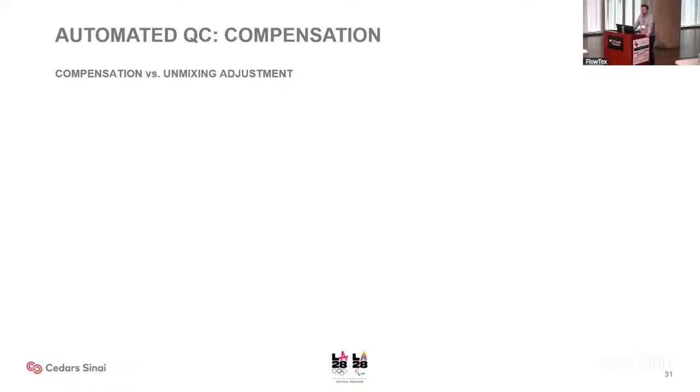In our lab, we see day-to-day drift, especially in the far red channel. So it's something that needs to be addressed. It doesn't limit our data interpretation the way it's at, but you do notice it. So it's something we're trying to work through. And how do we do this in a robust manner?